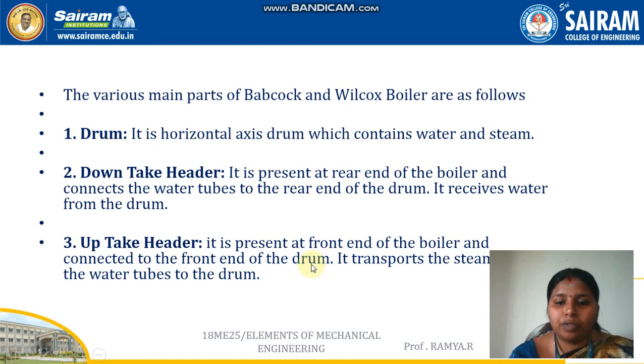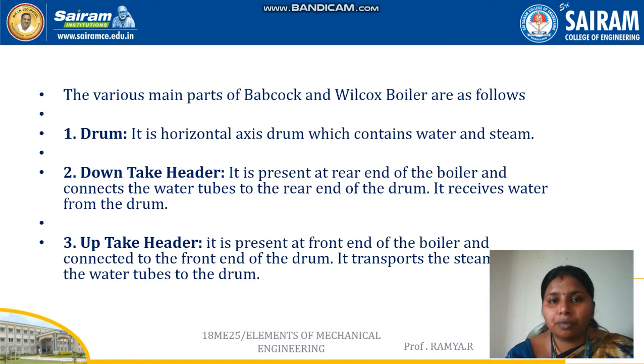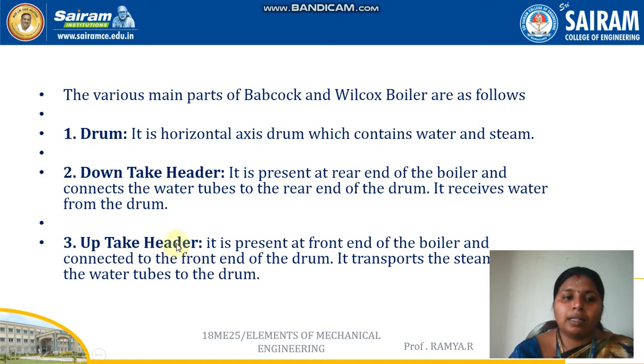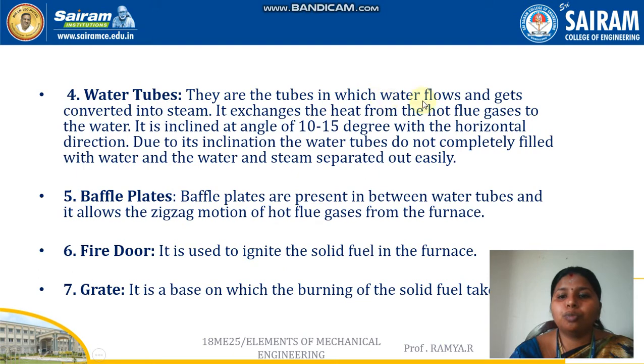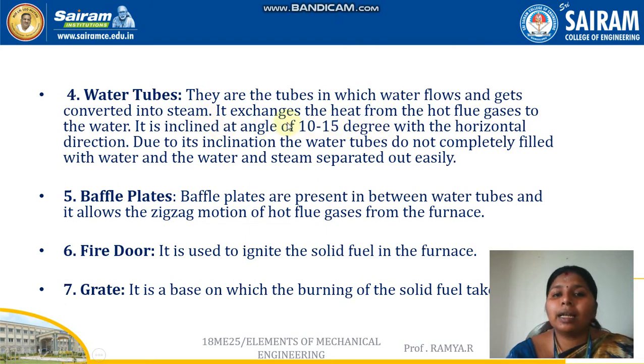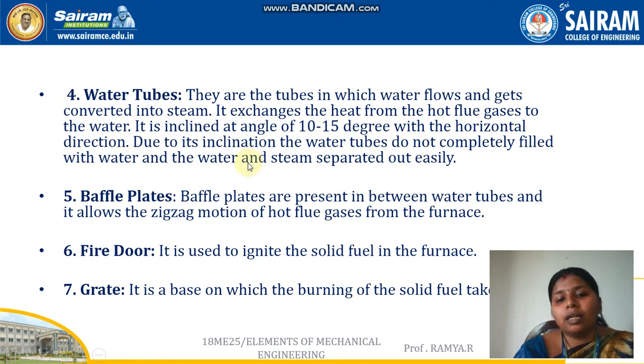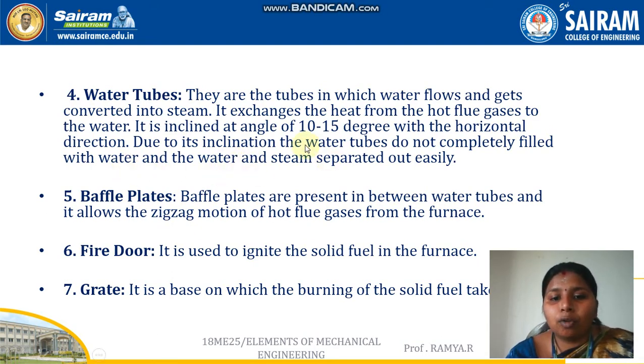The uptake header is present at the front end of the boiler, connected to the front end of the drum. It transports steam from the water tubes back to the drum. As water passes through the inclined tubes, the externally fired furnace heats it and converts it into steam, which is carried by the uptake header. The water tubes are inclined at an angle of 10 to 15 degrees to the horizontal so they are not completely filled, allowing steam generation inside.